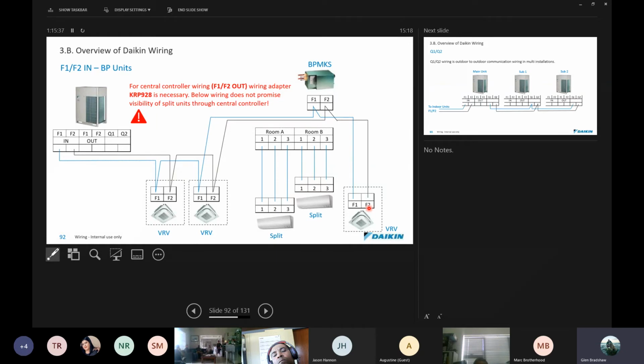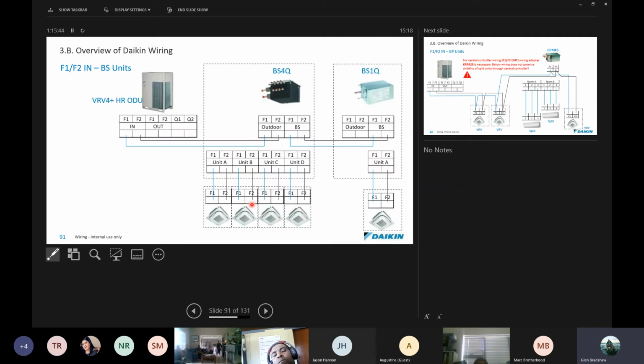Remember at all times, one of the most critical things, and I'm going to go back a slide, and then we'll come back to the slide as well. It's very, very important when connecting these up that your wiring for the A unit runs with the piping for the A port. If you start to swap these around on heat recovery systems, you're going to cause yourself a lot of nightmares. If 2 units are in opposite modes and their wiring is swapped, the cooling is going to go to the guy wanting heating, and this chap's heating will end up going to the guy who wanted cooling. And you're going to get a lot of nuisance calls until you get on top of the problem.